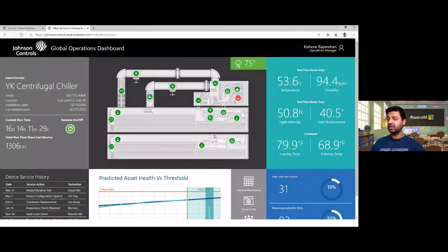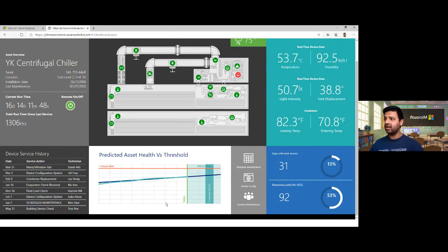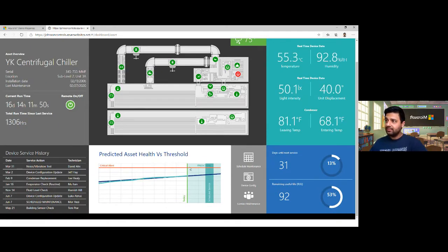So this is a digital twin, which is a physical system mapped digitally, and various sensors that are present in the HVAC system. Now, I don't see any errors here. Everything is working fine. The reason we have a critical issue flagged up is based on my predictive data modeling, so based on historical data that we've gathered and modeling that we've carried out. It is telling me that today we will have a critical alert coming through because over the next couple of days, there is a high chance of a part failing.